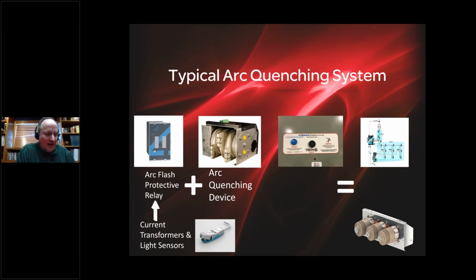If you're interested in the equivalent IEC standards and where they're at now, I know they just came out within the last couple months with a new edition. And there are differences between the IEC standard, I should note, and UL 2748. For example, the IEC standard defines that the voltage drop across the arc quencher cannot be more than 34 volts. So, for example, the Eaton device, which injects a purposeful impedance, could not meet the IEC standard, whereas our device, which effectively drops the voltage to zero between the phases, meets both standards. So a device like ours had to be designed specifically to meet both of those standards.